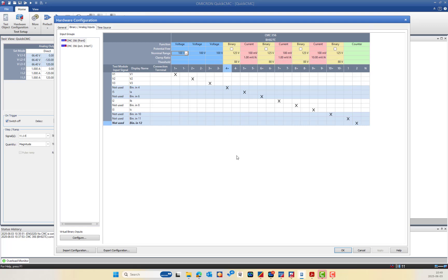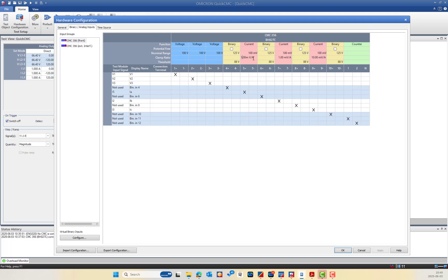Regarding the current, I will use binary input number 5 for IA, number 7 for IB, and number 9 for IC — not in the same pair. For current, there are two settings: the nominal range and the clamp ratio. If you are using a 1 milli-ohm shunt resistor, adjust the clamp ratio to 1 millivolt per ampere, which corresponds to the 1 milli-ohm shunt resistor.